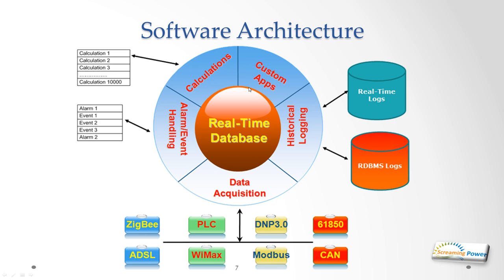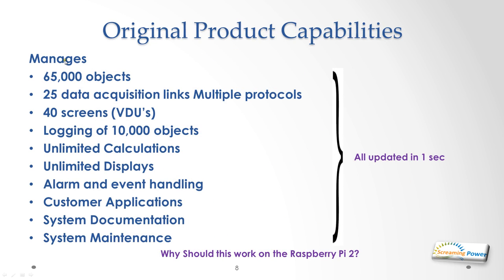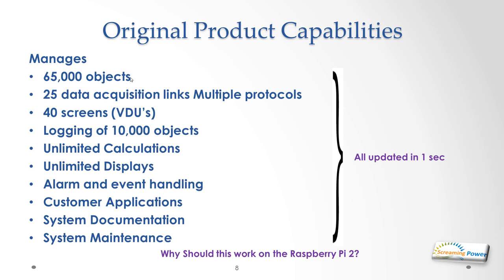The product capabilities originally were that it handled 65,000 database objects, in other words 65,000 values either coming from the field or as a result of calculations. Some people call those tags. They were acquired from up to 25 data acquisition links with multiple protocols and different numbers of nodes on the link. We could drive up to 40 VDU screens. We could log up to 10,000 objects in the database at frequencies from anything from cyclic frequencies of one second up to one year. We could do unlimited calculations, unlimited number of displays in the system, very comprehensive alarm event handling package, the ability to integrate customer applications, and of course the system was self-documenting and also came with a complete suite of maintenance facilities to be able to build your applications.